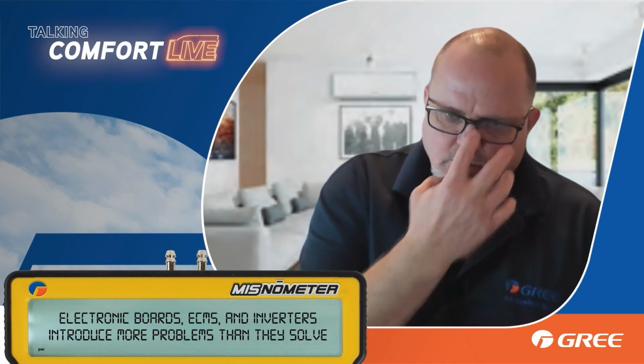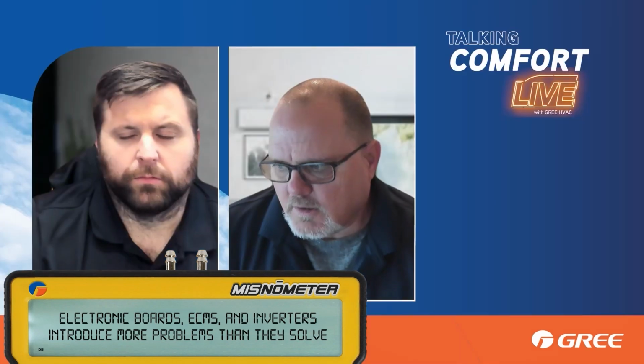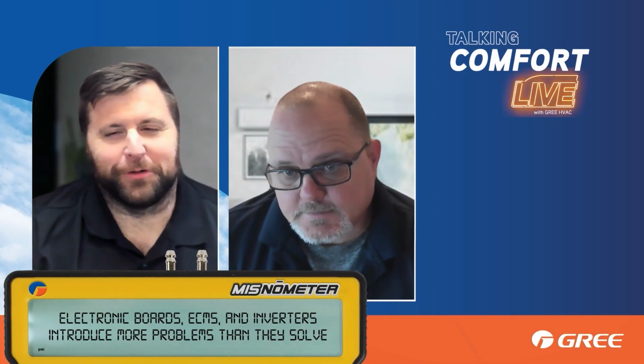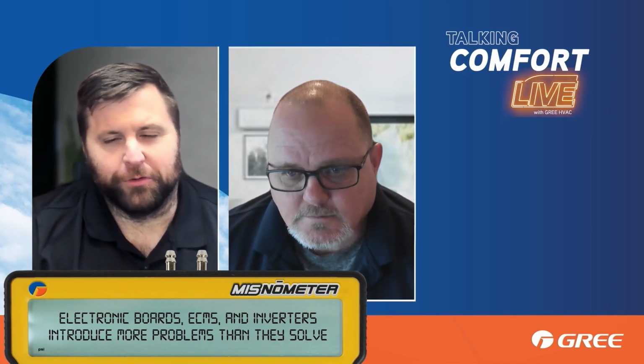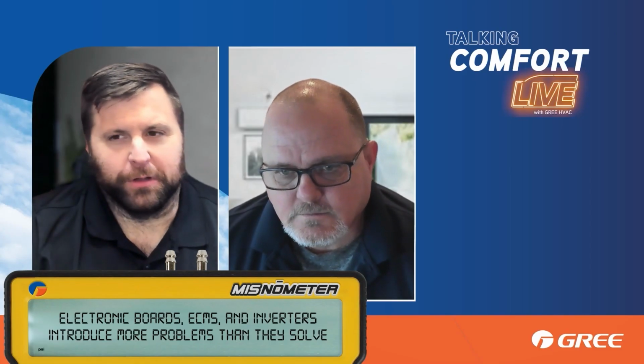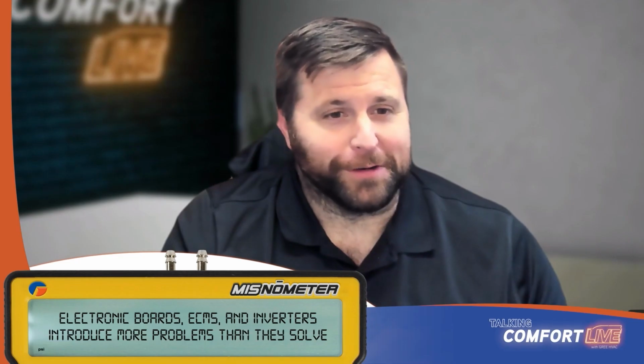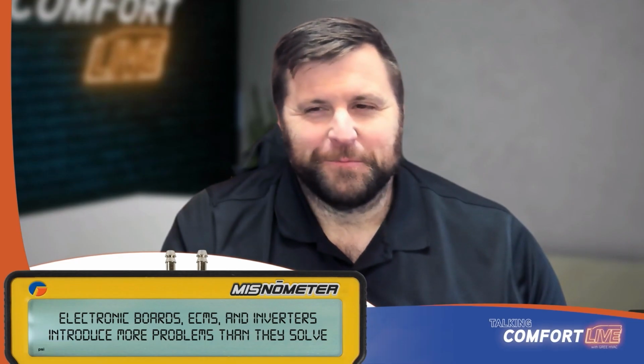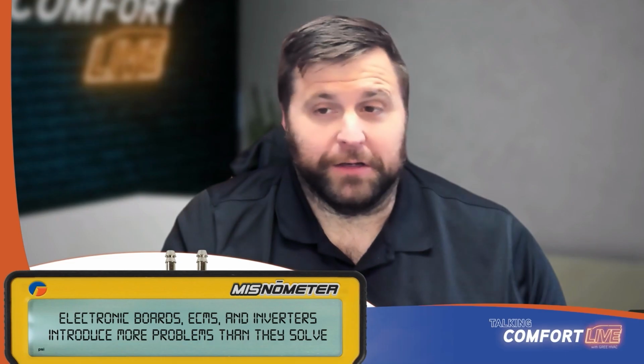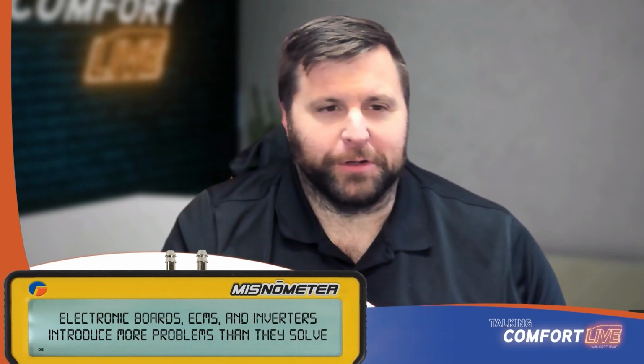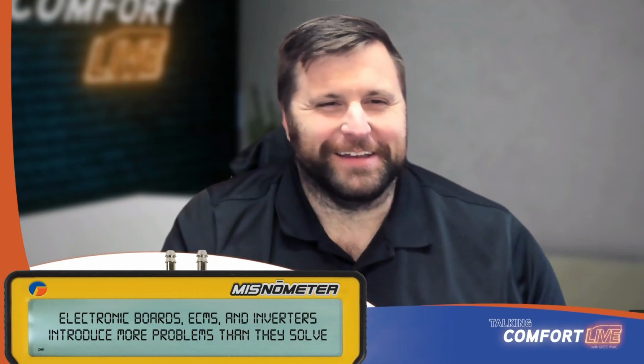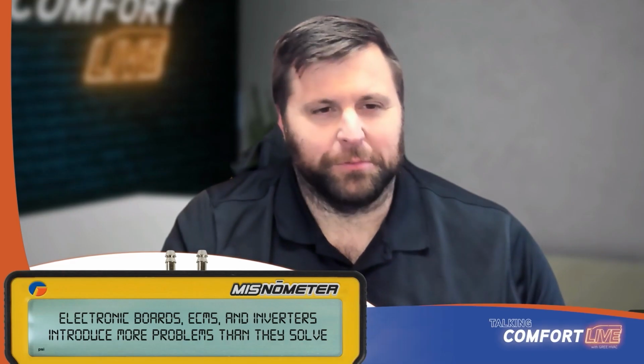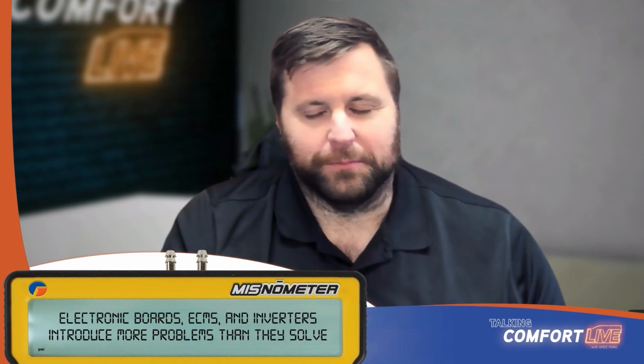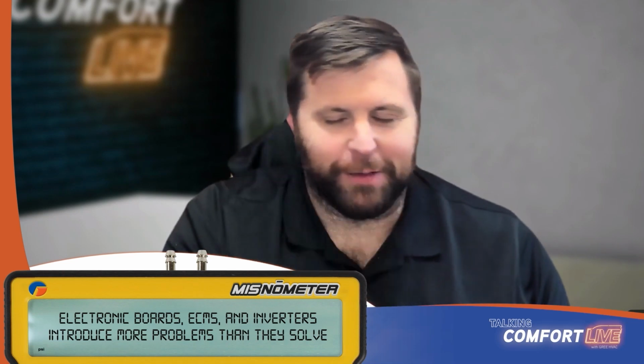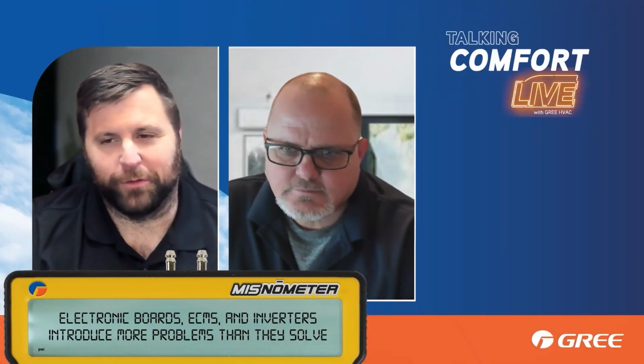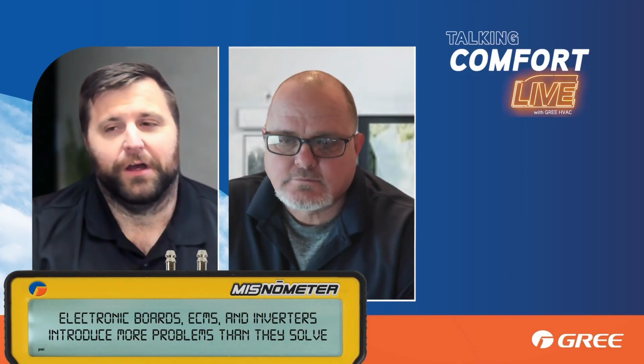Mm-hmm. Well, I think another good point, something that we came into more contact with, I guess, with our Flex system when it was introduced, a few years back, is that we were dealing in a hell of a lot more duct work than what we had done before. And we kept finding, not you guys watching the video, of course, you guys are great, but there are many folks out there that would not set the blower speed, would not try to use a manometer to determine what their static pressure was, what their expected CFM should be, that kind of thing.